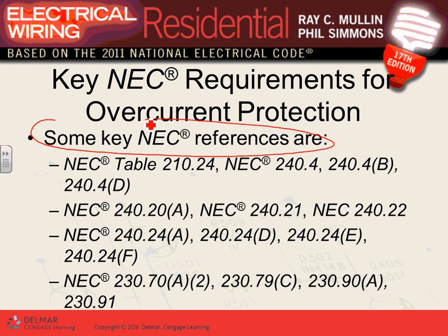A number 14 conductor — you cannot land more than a 15-amp fuse on it. Section 240.4(D) tells you that number 10, 12, and 14 conductors have limitations of 30, 20, and 15 amps respectively.